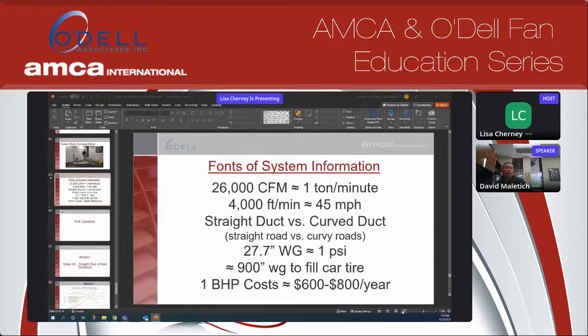Okay. When you're moving 26,000 CFM through a fan, you're functionally moving 1 ton of air through the fan every single minute. So every 3 minutes, you're practically moving a pickup truck through that fan. Another way to look at it is that each cubic foot of air at standard conditions weighs 0.075 pounds per cubic foot. Sometimes I think that putting that extra decimal in there makes it unrelatable. But if you think about it, you need about 13.1 cubic feet to make 1 pound of air. And most mid-sized cars have a trunk that's around 13 cubic feet. So when you're driving your car around, if you have a mid-sized car, you're functionally driving around with 1 pound of air in the trunk at any given time.